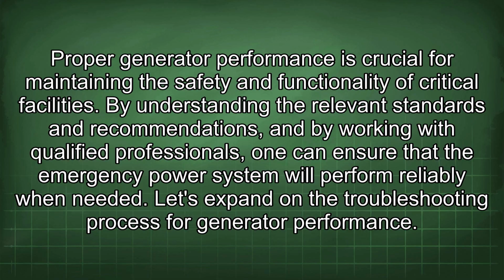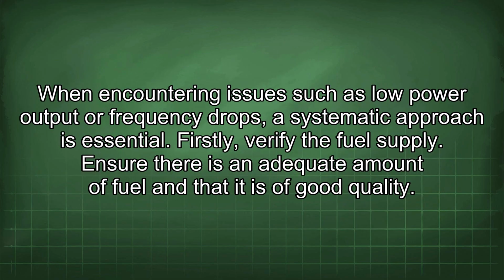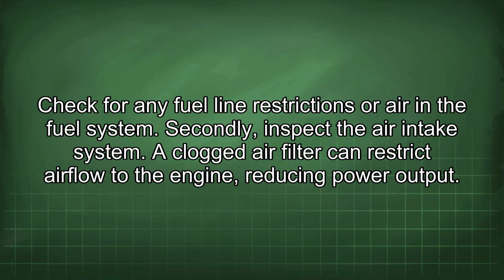Let's expand on the troubleshooting process for generator performance. When encountering issues such as low power output or frequency drops, a systematic approach is essential. Firstly, verify the fuel supply. Ensure there is an adequate amount of fuel and that it is of good quality. Check for any fuel line restrictions or air in the fuel system. Secondly, inspect the air intake system. A clogged air filter can restrict airflow to the engine, reducing power output.